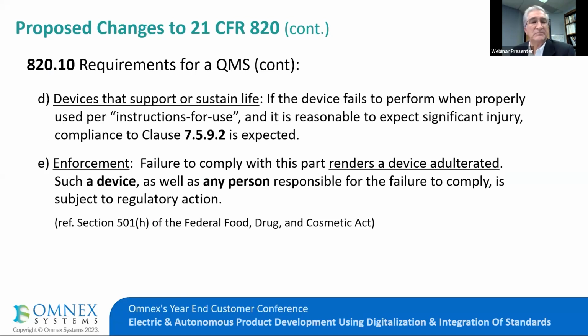Okay, paragraph D. Devices that support or sustain life, if the device fails to perform when properly used, it is reasonable to expect significant injury. Compliance to 7.5.9.2 is expected. That is particular requirements for implantable medical devices.